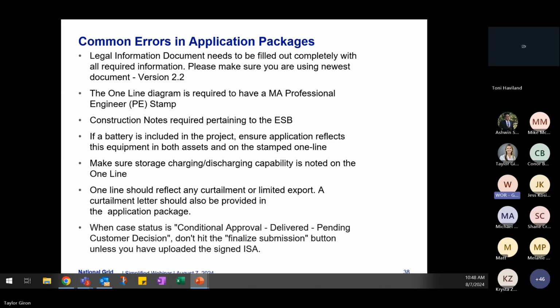If there's a battery on the project, ensure that the application reflects the equipment in both the assets and the stamped one line. So everywhere in the case, we need this to agree. Make sure the storage and charging/discharging capability is noted on the one line. The one line also should reflect any curtailment or limited export. A curtailment letter is required to be in that application package. When the case is in conditional approval delivered, pending customer decision, don't hit finalize submission until you've uploaded the signed ISA. Otherwise, we'll have to reopen it and start over.